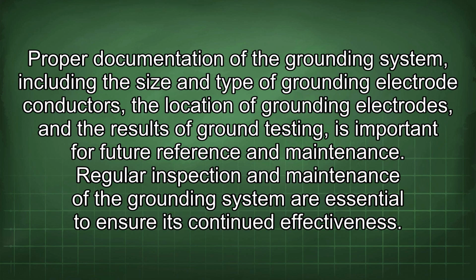Proper documentation of the grounding system, including the size and type of grounding electrode conductors, the location of grounding electrodes, and the results of ground testing, is important for future reference and maintenance. Regular inspection and maintenance of the grounding system are essential to ensure its continued effectiveness.